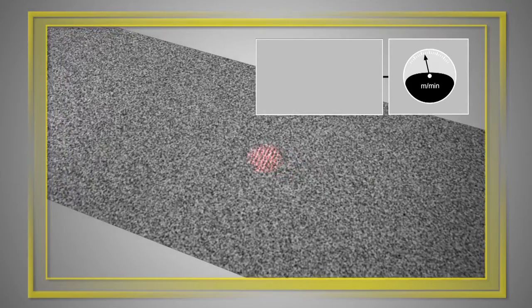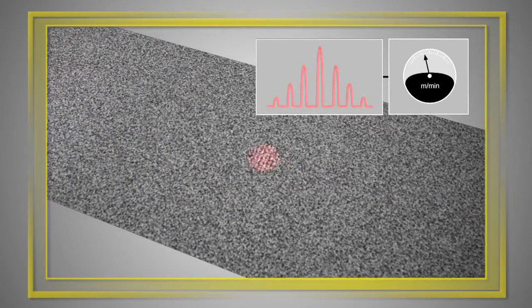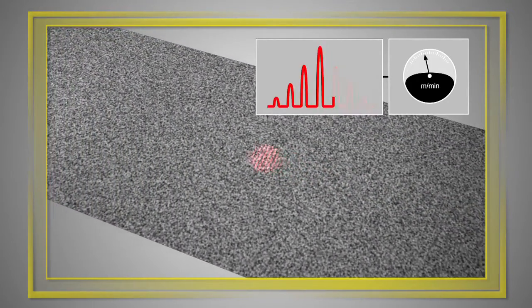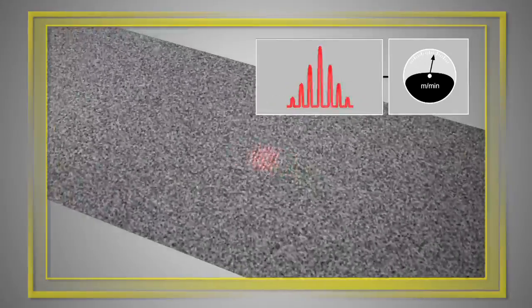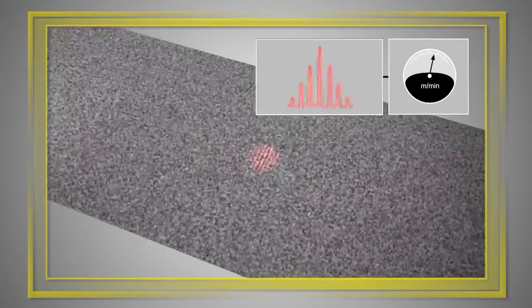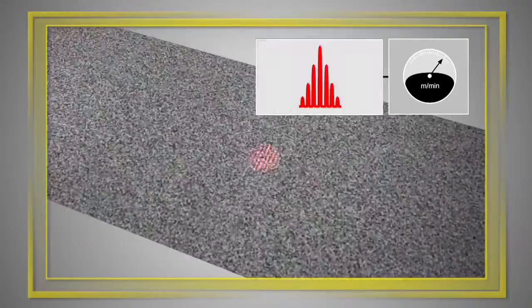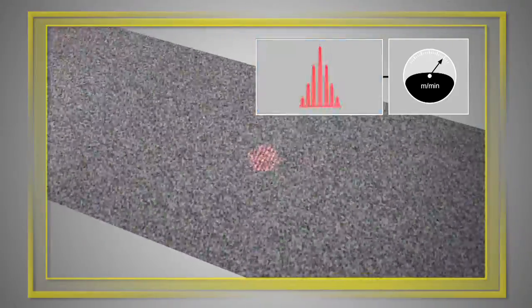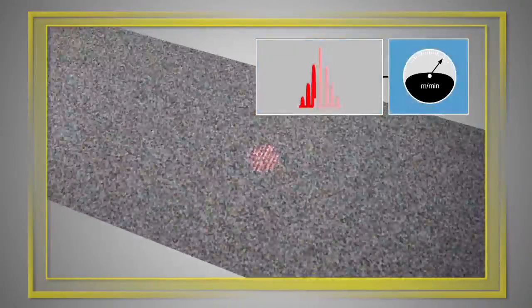As the surface moves through the fringe pattern, the intensity of the light scattered from the surface modulates in frequency. This modulation frequency, measured by the sensor's photoreceiver, is directly proportional to the surface velocity.